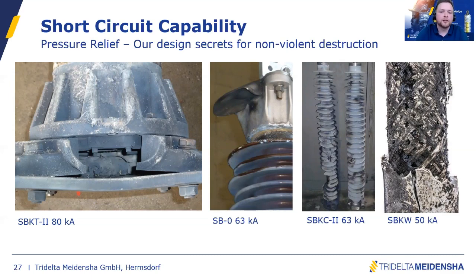very hot gas, and also for the surge arrestors with gas volume, naturally this enclosed air will try to expand and will put pressure on the housing. And this can be very, very dangerous, especially for porcelain housed surge arrestors. In the past decades, people learned the hard way that especially porcelain housed surge arrestors can explode like a bomb, and all those fractured parts will fly around and destroy everything in the surrounding. So we have to make sure that this doesn't happen.